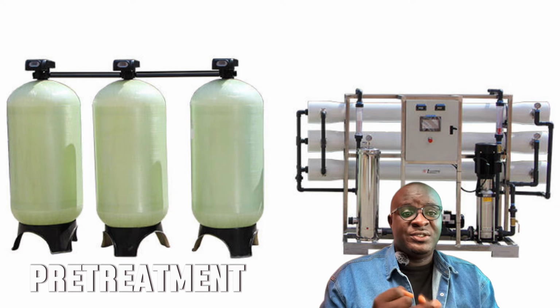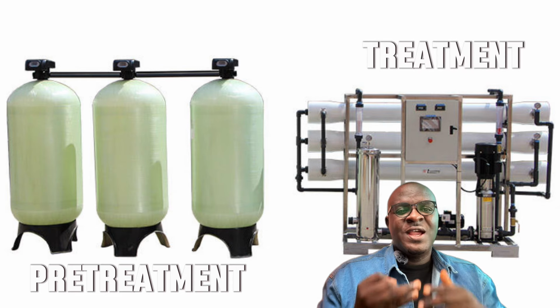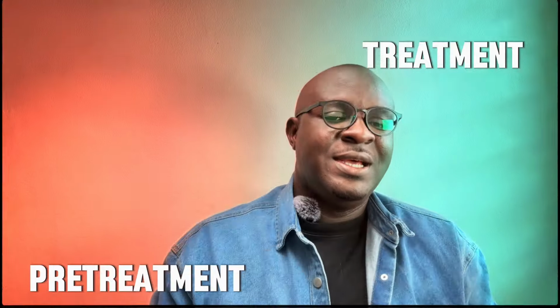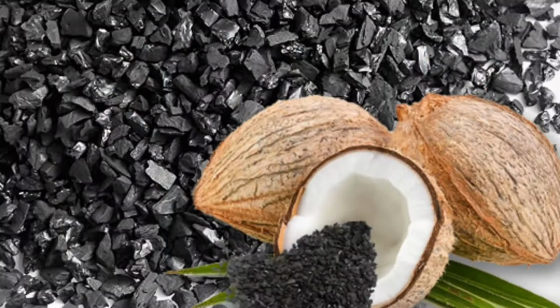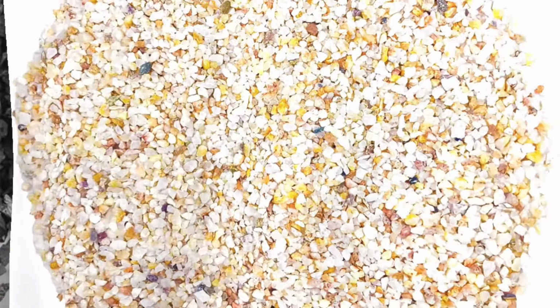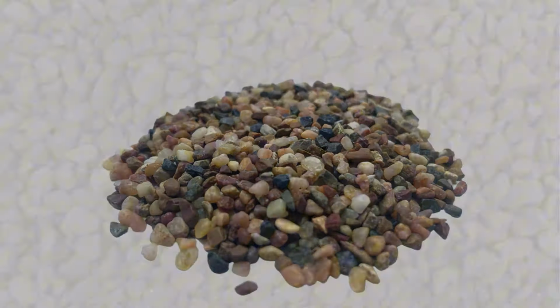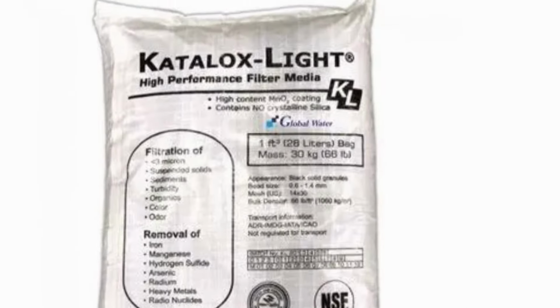Every reverse osmosis system is divided into three main parts, right? A pre-treatment, the treatment, which is the reverse osmosis itself, and the post-treatment. The pre-treatment comes with the multimedia system: activated carbon, silica or quartz sand, gravel, that's filtration gravel, manganese dioxide, Katalox, Prolox, Manganox, Aquanox, name them. All those things are for removal of iron, removal of manganese, and removal of suspended solids from the water.